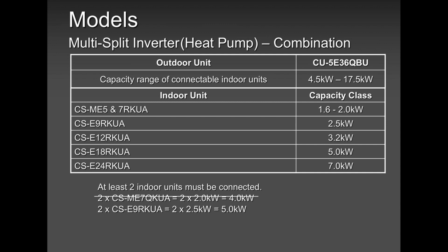But please don't buy a 36,000 and just put two 9,000s. Money wise, economy wise, that's not good. I always tell guys, when you're buying a multi-zone, utilize all the ports. If need be, utilize all the ports. The customer has paid top dollar, so utilize all the ports. And here is the conversion between kilowatts and BTUs. 3,412 BTUs per hour is equal to 1 kilowatt. So if you had a 36,000 BTU, I would pick a 9,000, a 12, a 7 and a 5 here and there. But don't just put an 18 and a 24, even though the catalog says that.